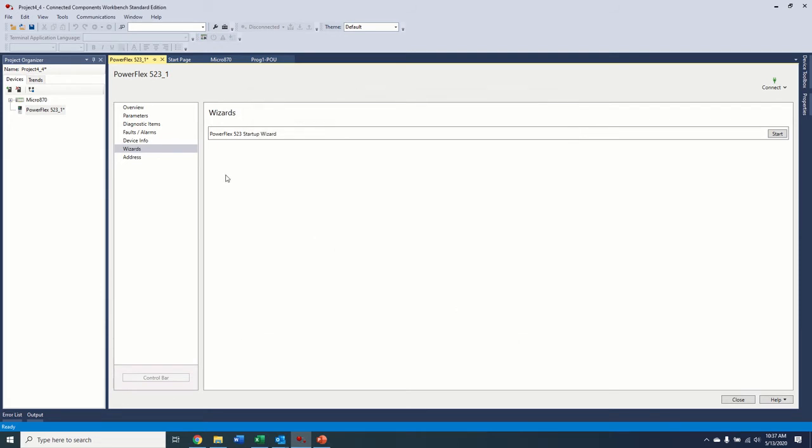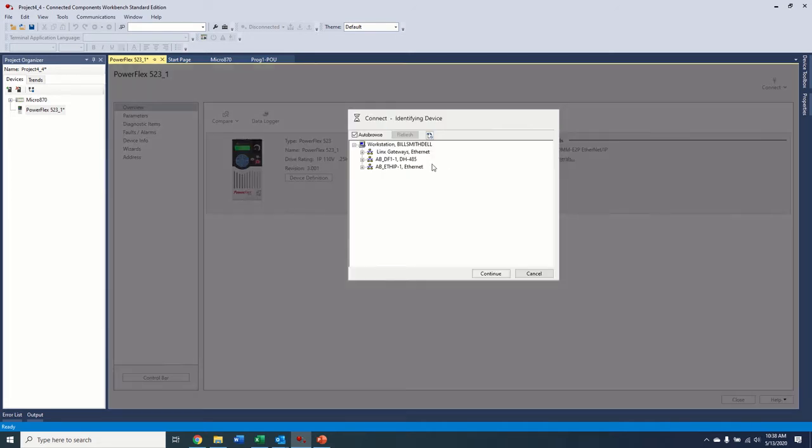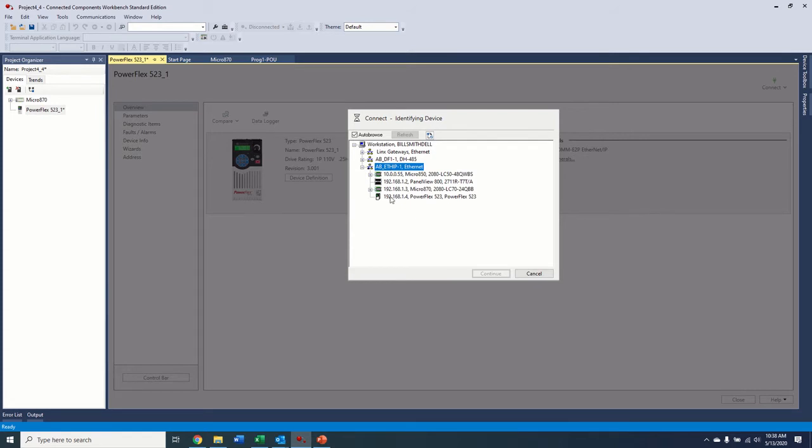We weren't online with the drive. We didn't make any actual changes to the drive. I do have a 523 sitting here. So the first thing I'm going to do is I'm going to go up here to connect. I know that my drive is right here at .4 on the Ethernet. So out of the box, obviously, unless you have a managed switch with port persistence, the drive is not going to have an IP address. So you have a couple options there. Either use a managed switch that would assign it its IP address.